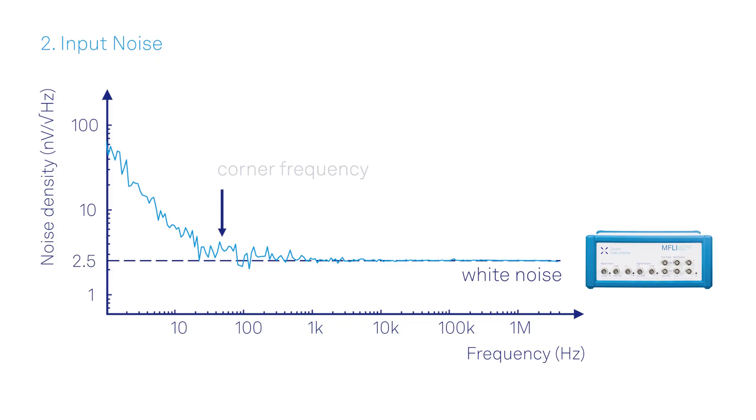Below the corner frequency, the voltage noise density scales typically as the inverse of frequency. For best results, you should consider an instrument with a corner frequency lower than your target frequency and a low and flat noise floor to minimize the disturbances in your measurement.